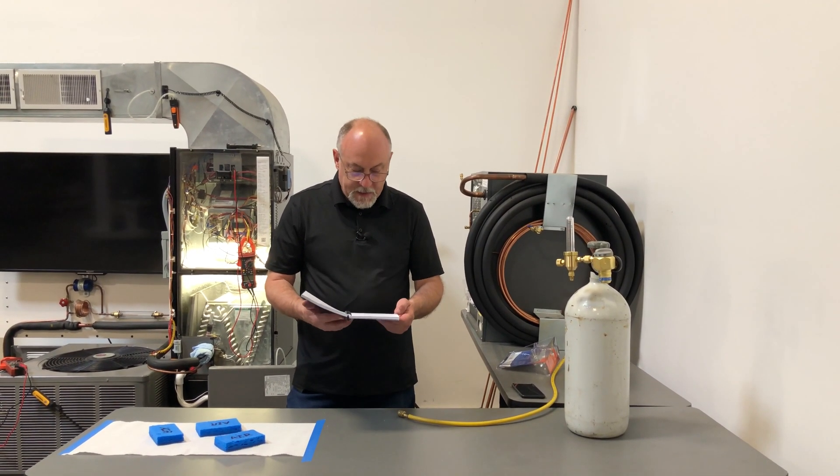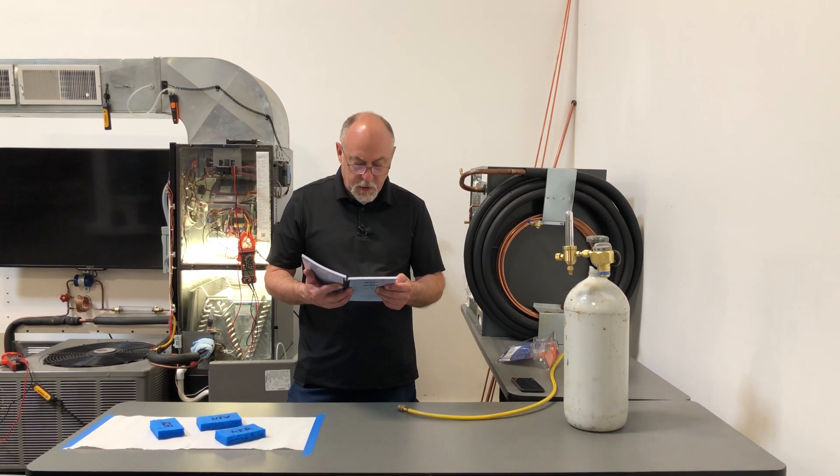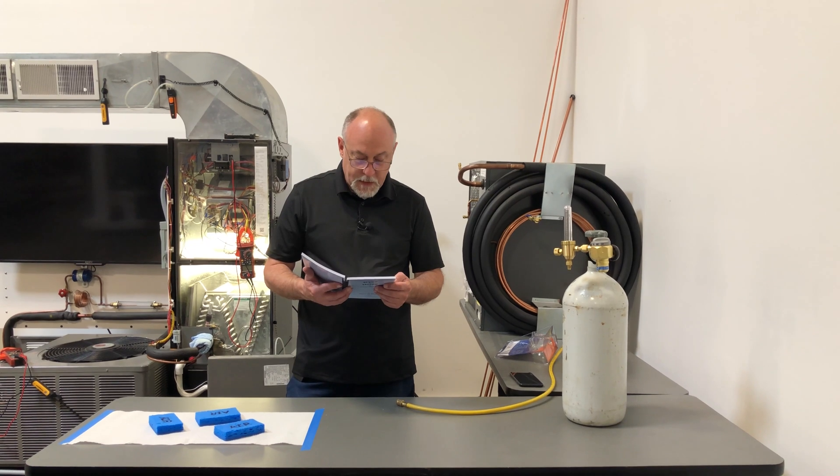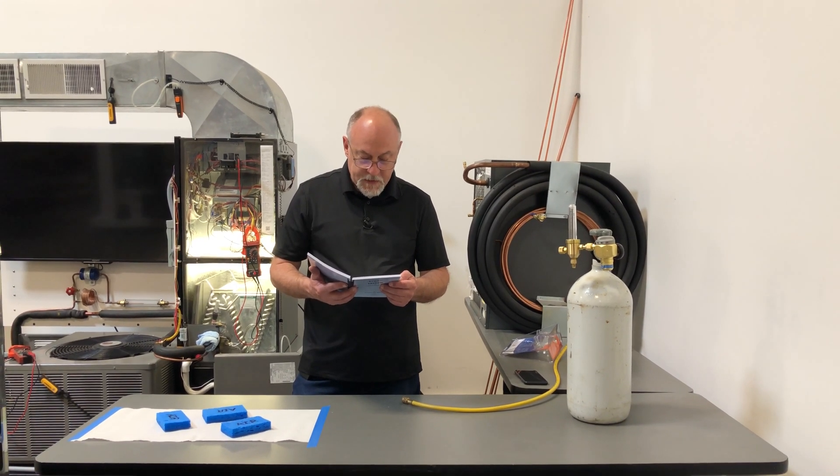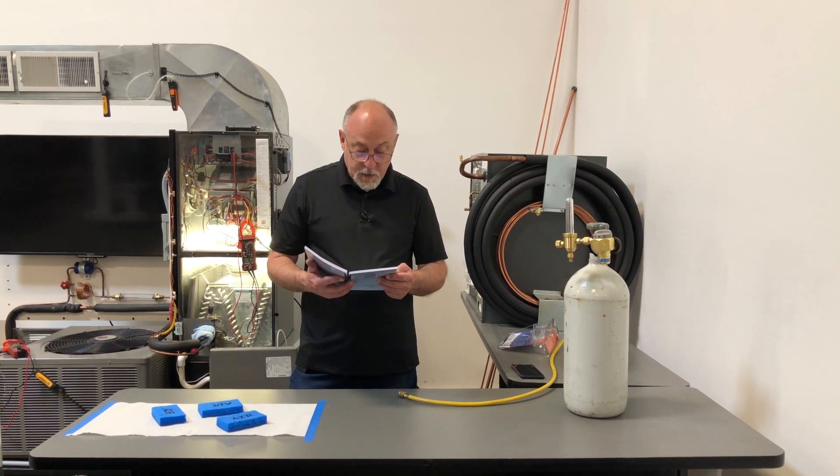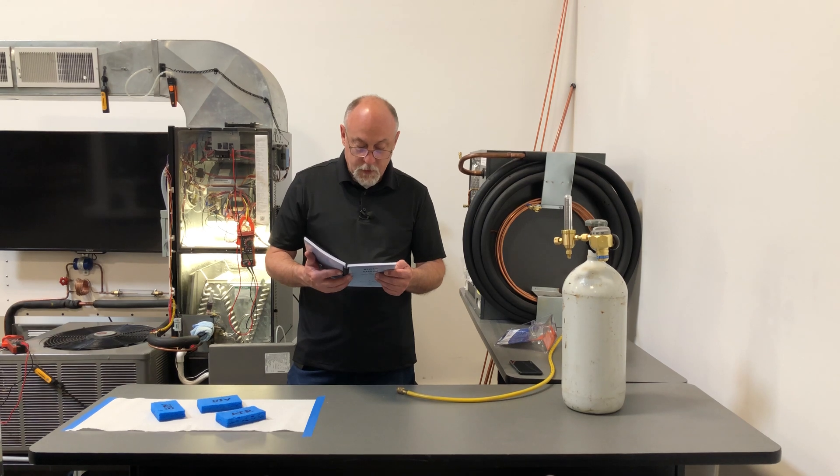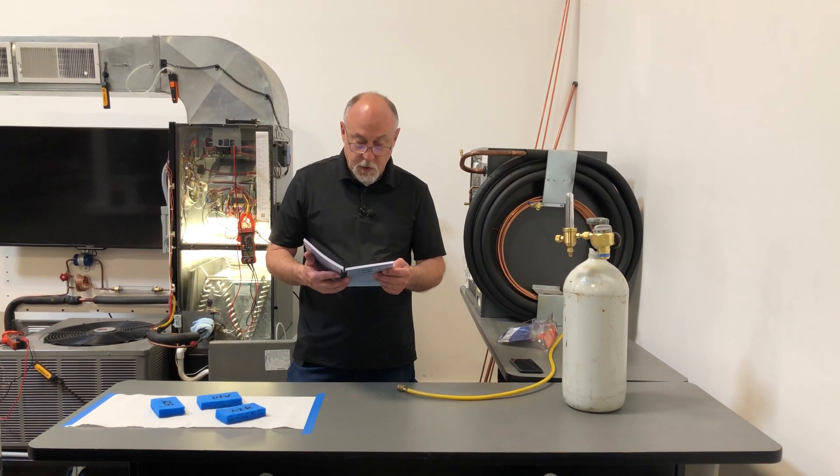If you go to page 70 of the guide, it says after the lines to the various refrigeration cabinets have been installed, it's necessary to purge them to make sure they're not clogged up. Purge with a dry gas such as anhydrous nitrogen or carbon dioxide. This will not only blow out some of the atmosphere or droplets of water but also pick up some of the moisture.